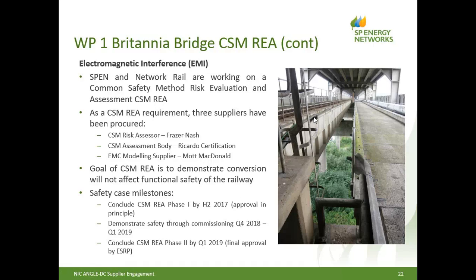So this has caused us really to get into something which Network Rail operate called a common safety method risk assessment and evaluation. What that means is that we basically need to risk assess and consider all the potential risks that operating the existing circuit at DC may present to the railway, and have that verified, go through an assessment with the Network Rail expert panel of engineers, and hopefully come out at the end of it with agreement that we've managed the risks and we're not going to cause any problem. So I won't go through the wording of this slide, because I've got a small slide shortly which shows you the flow path for this, so hopefully it'll make a bit more sense then.